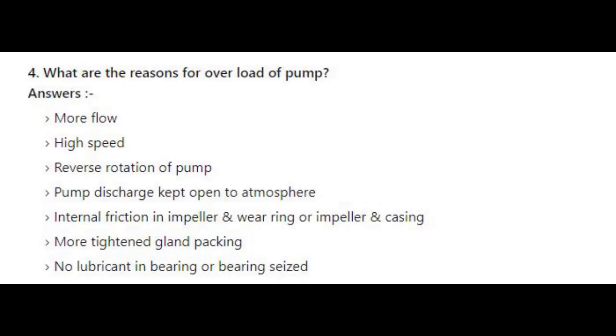Number 4: What are the reasons for overload of a pump? More flow. High speed. Reverse rotation of pump. Pump discharge kept open to atmosphere. Internal friction in impeller and wear ring or impeller and casing. More tightened gland packing. No lubricant in bearing or bearing seized.